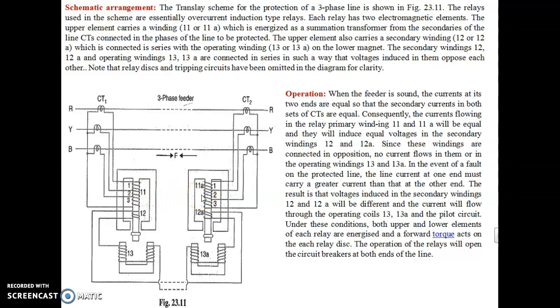Okay, but these windings are connected. Next, they will induce equal voltage in the secondary. Secondary means 12 and 12A. They induce voltage at the secondary, but the secondary winding 12, 12A is connected in series opposition with 13 and 13A, that is the operating coil. Here series opposition means there is no induced current in this operating coil, that is the lower magnet. There is no current flowing in that. Hence there is no flux produced in the lower magnet. Is it clear? So there is no current flow through the operating coils 13 and 13A.